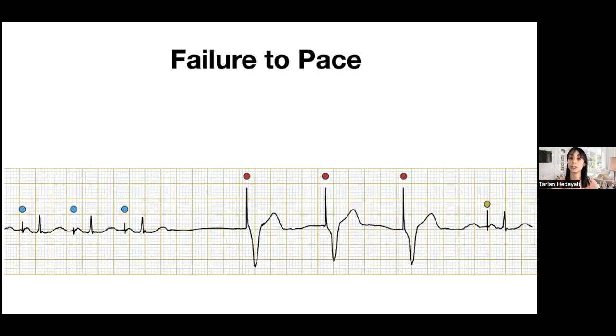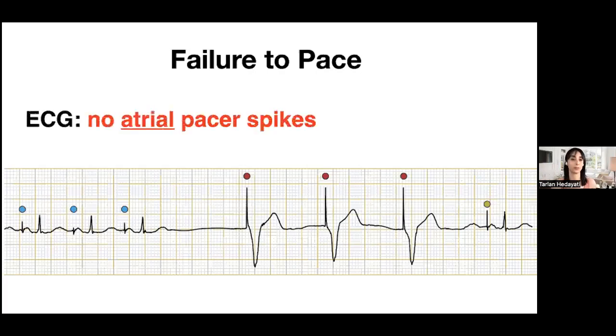Okay, so patient's very fortunate. They have a dual chambered pacemaker. When that atrial lead failed, the ventricular pacemaker was able to take over. So in this particular case, this was a failure to pace of the atrial pacemaker.